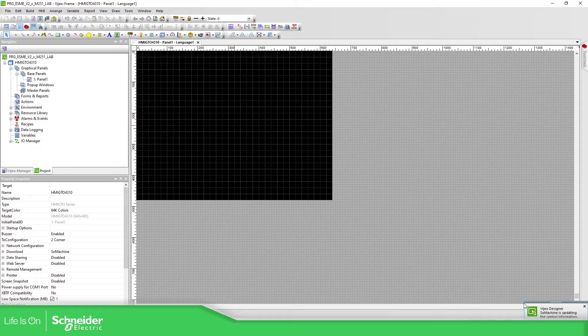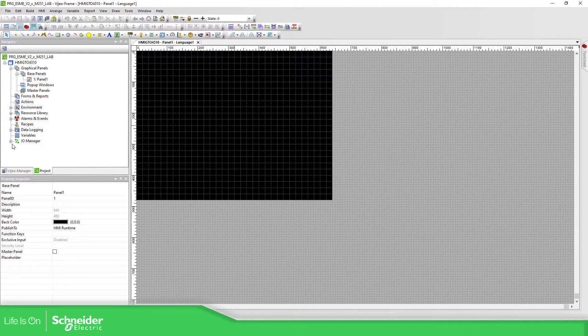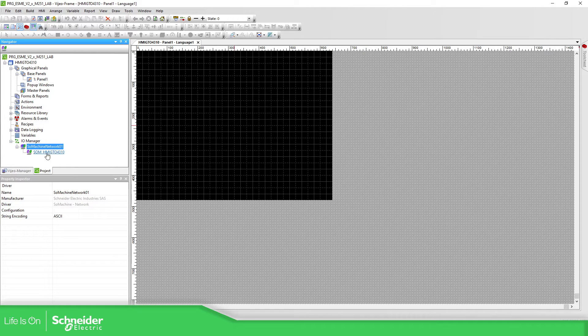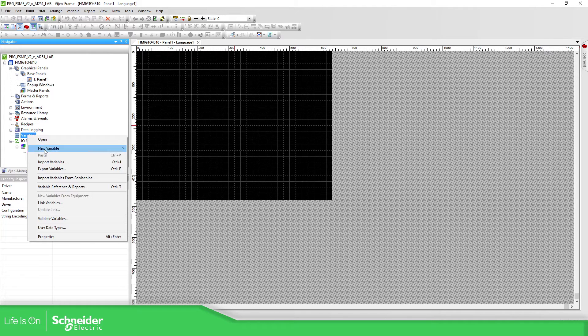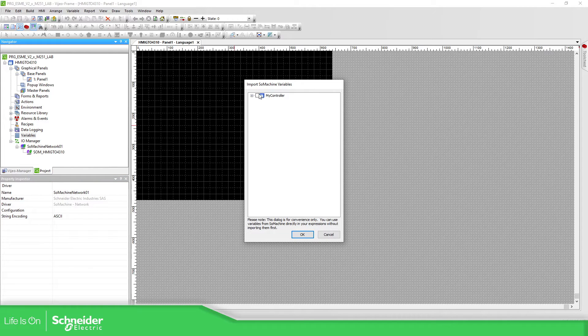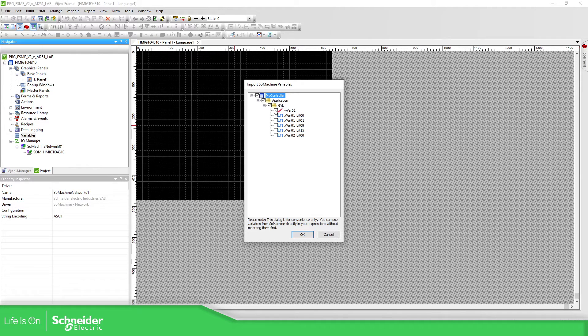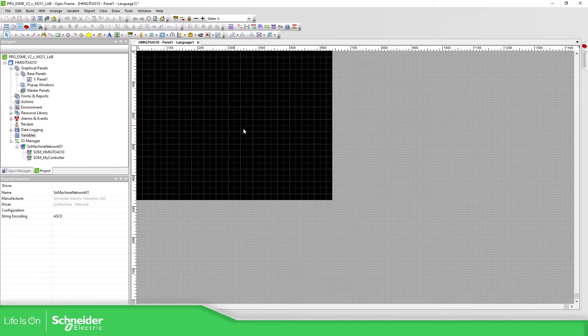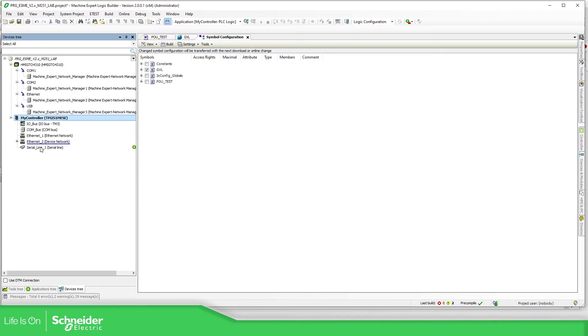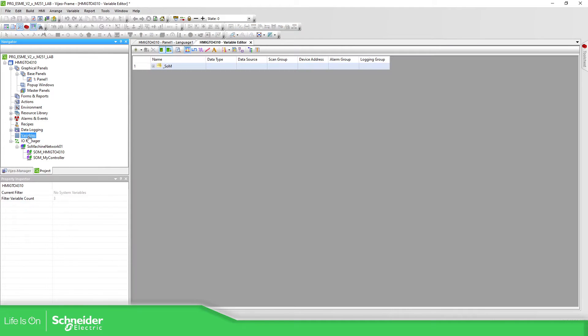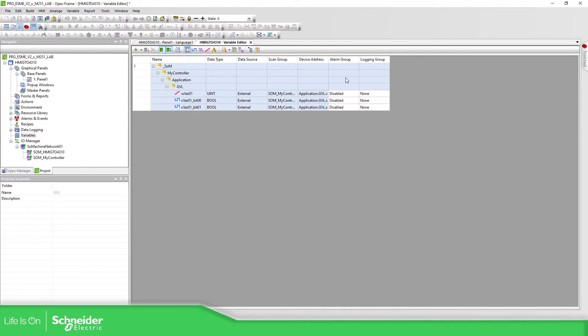On the HMI side, we should be able to see Vijeo Designer. The machine name has been updated — even if it says SoMachine, now it's Machine Expert. On the IO manager, we should be able to see the HMI. What we need to do is go to Variables, import variables from SoMachine — even if it's Machine Expert. Here we just need to select the target, and from the list of variables we can select all of them or some of them. In our case, we're going to select these two. Once you add variables to the project, you can see a new device has been added — My Controller — which is the device over here. If we go to Variables again, we should be able to see the list of variables that we have added.